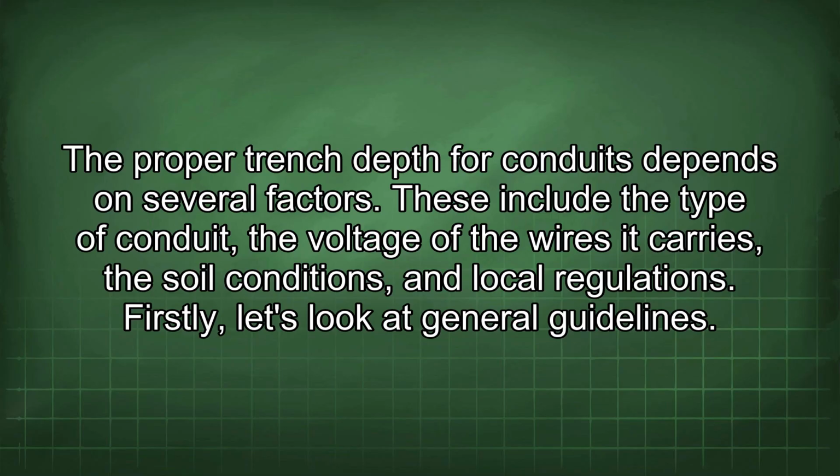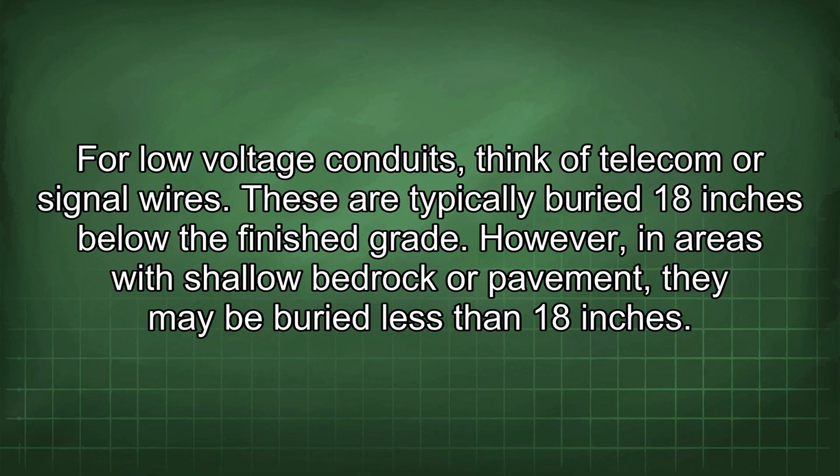Proper trench depth for conduits depends on several factors. These include the type of conduit, the voltage of the wires it carries, the soil conditions, and local regulations. Firstly, let's look at general guidelines. For low-voltage conduits, think of telecom or signal wires. These are typically buried 18 inches below the finished grade. However, in areas with shallow bedrock or pavement, they may be buried less than 18 inches.